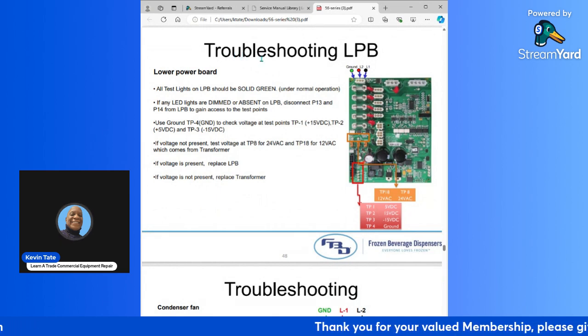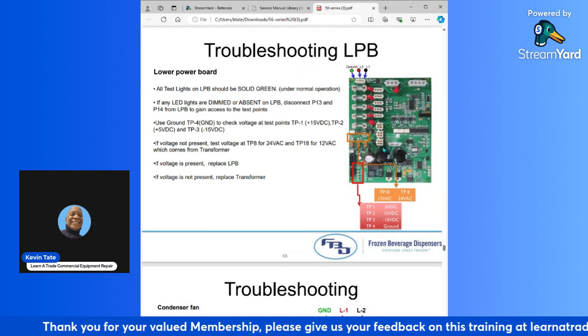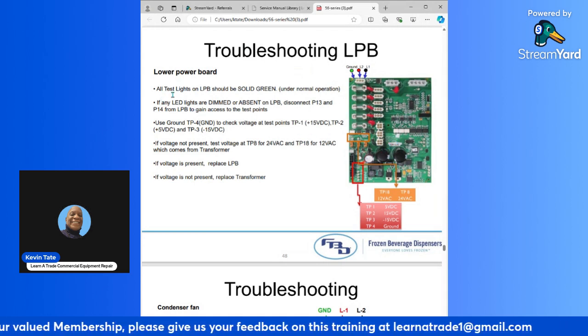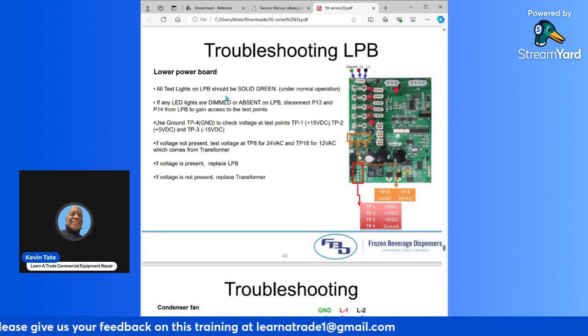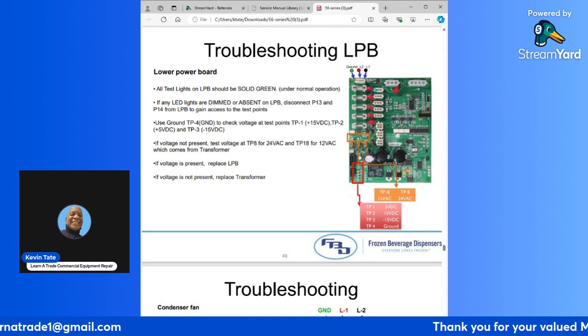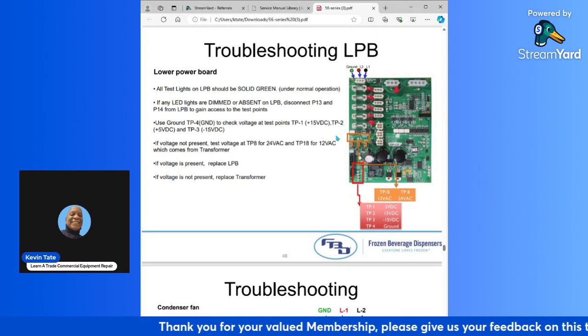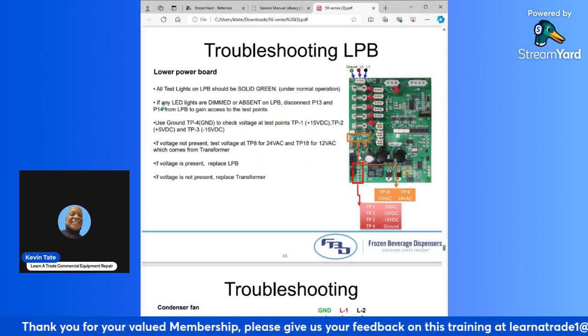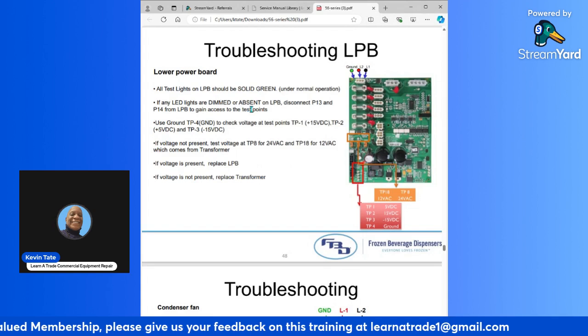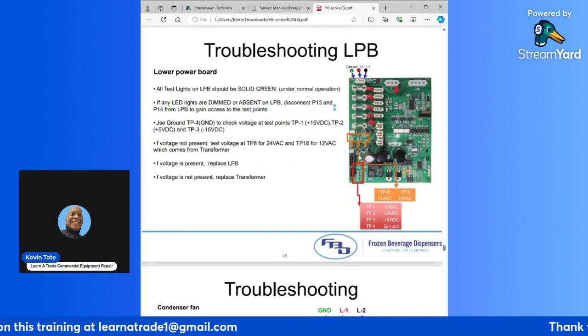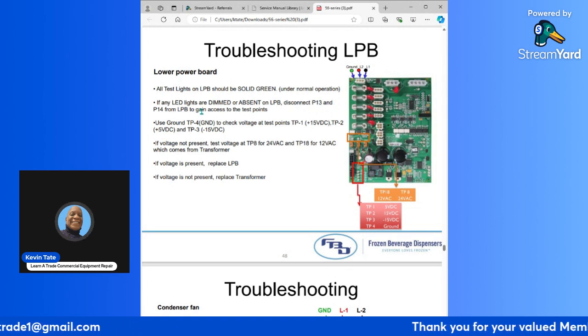Next, we're going to troubleshooting the lower power board. This will be your lower power board. All test lights on the lower power board should be solid green under normal operation. So all of the test lights should be solid green, okay? If any LEDs are dimmed or absent on the lower power board, disconnect P13 and P14 from the lower power board to gain access to the test points.